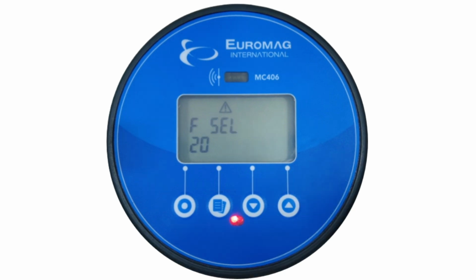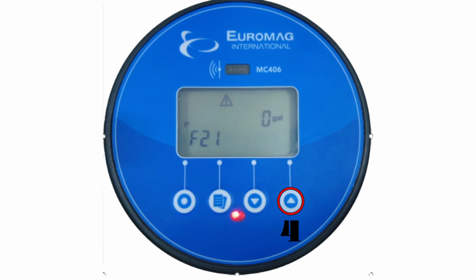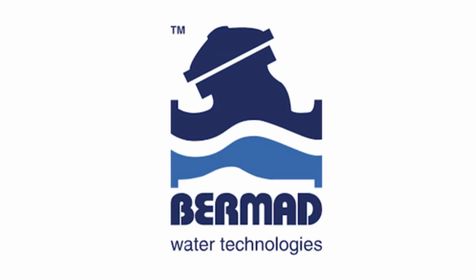The last two functions we will cover in this video will be number 20 and number 21. These functions will reset the partial totalizer and reverse partial totalizer. To reset the current values shown, simply navigate to function 20 or 21 and hold the number 4 button for 5 seconds or until the value changes back to 0. The remaining functions number 22 through number 29 do not need to be adjusted.